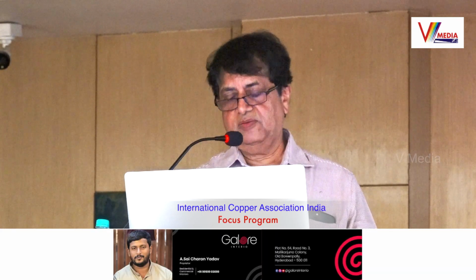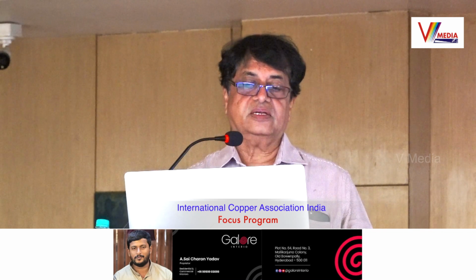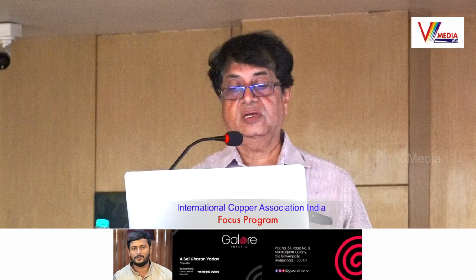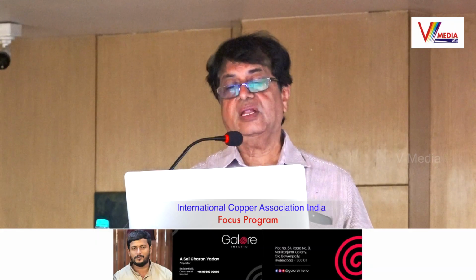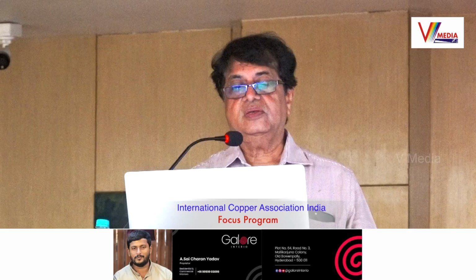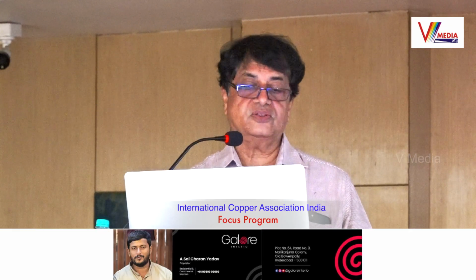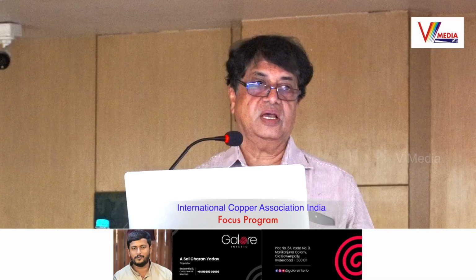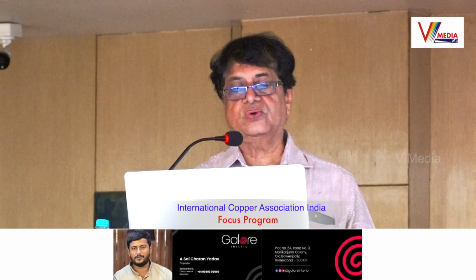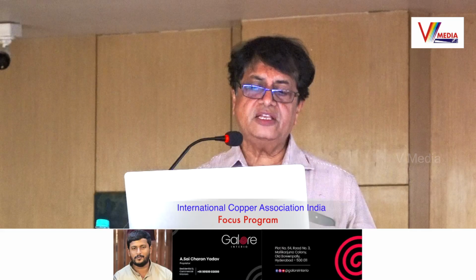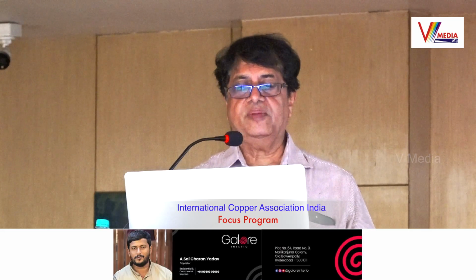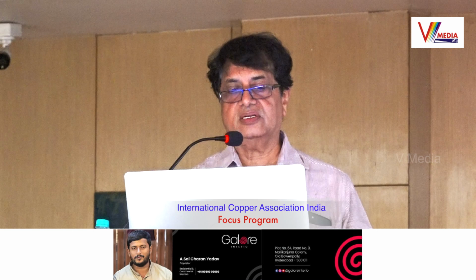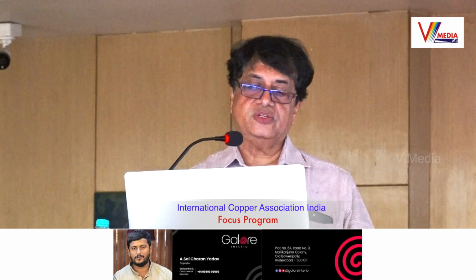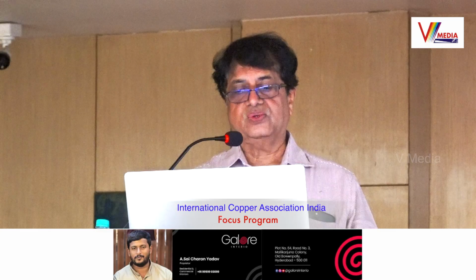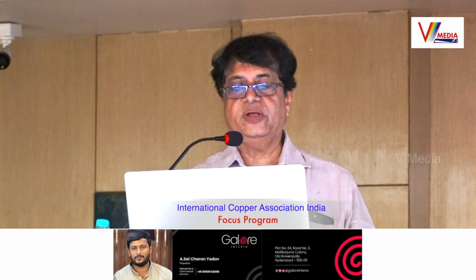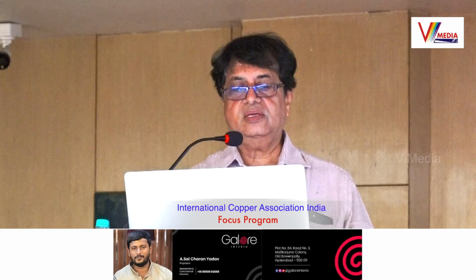One more point of conflict between the architect and the electrical provider of a lightning protection system is that architects many times do not allow the down conductors to be taken along the surface of the building, because that damages the aesthetics of the building. But as per the standards and codes, that is necessary, and it has to be taken from the surface of the building. Certain parameters are there: how much clearance should be maintained between two down conductors, how many conductors are required, how the earthing pit should be designed. All these details are given in the standard. So this is the inherent part. There should be some better way found at the time of planning itself, of how the down conductors should be taken.